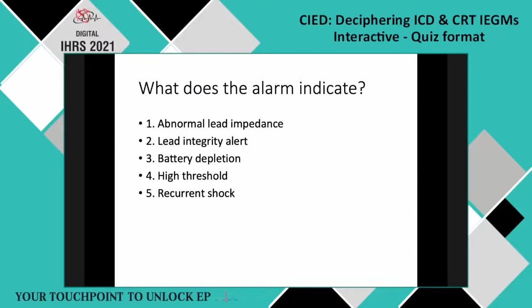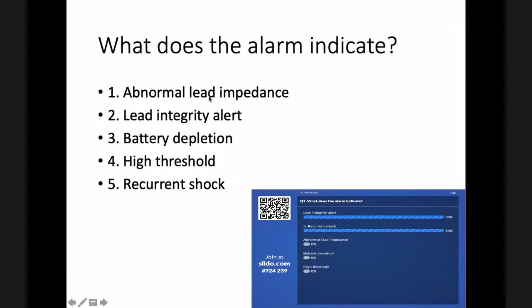Any voting has come? Actually, there are multiple options that are correct in this. Yeah, so it is option 2 and option 5 that people have selected. Okay. So the right answer is actually 1, 2, and 3. So in Medtronic devices, if you have abnormal lead impedance that is out of range, this kind of alarm comes. Second is, even if the abnormal lead impedance is not out of range, but there is a lead integrity issue, there are 3 criteria in that. We might discuss if time permits.